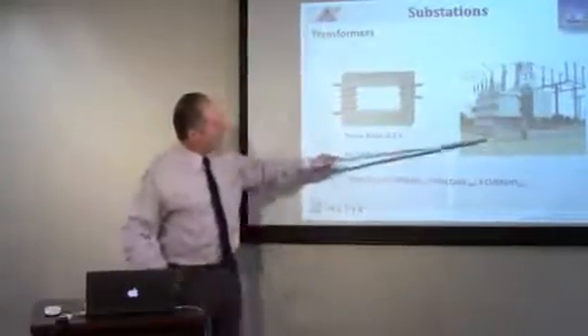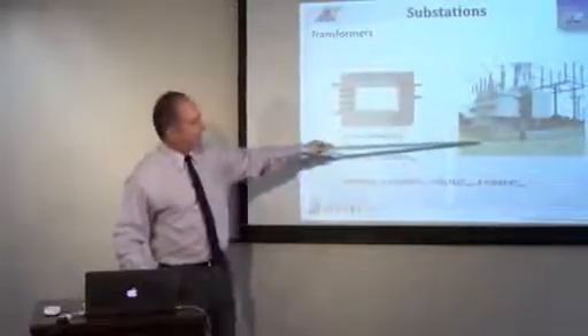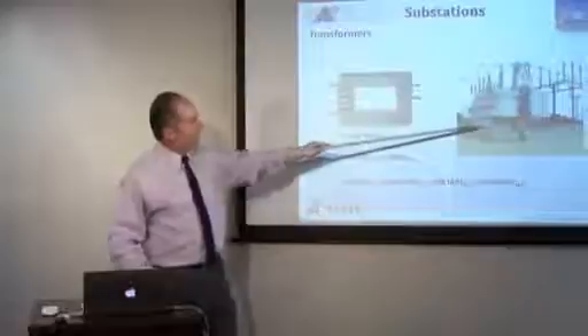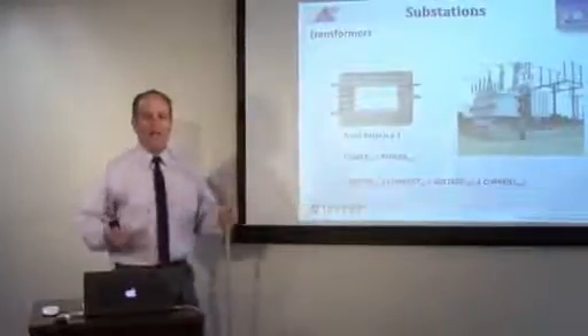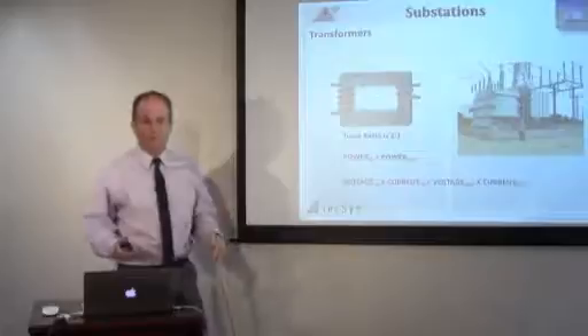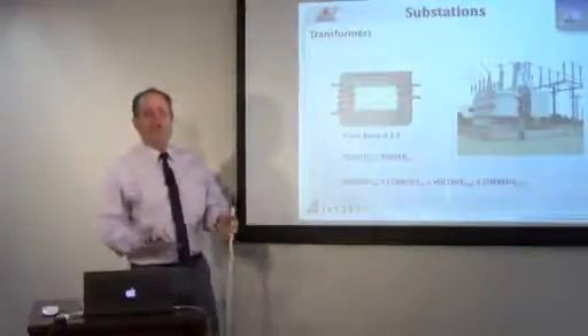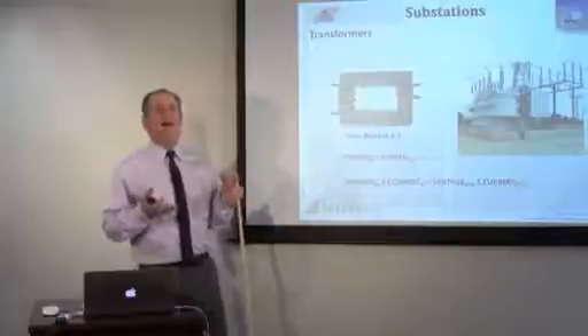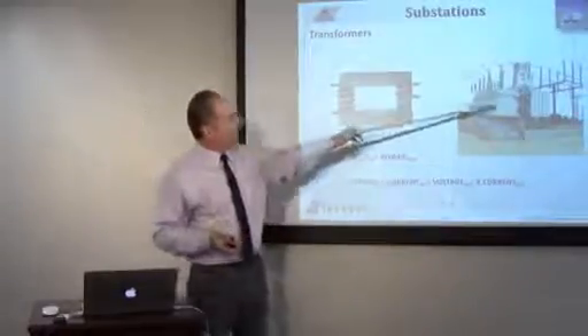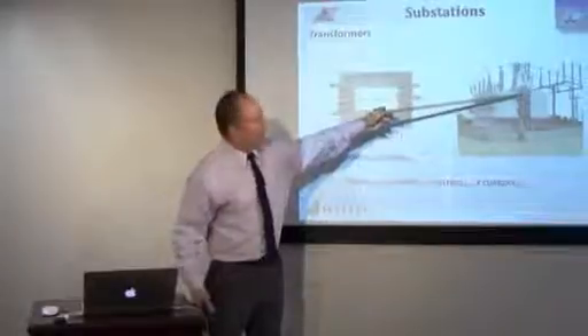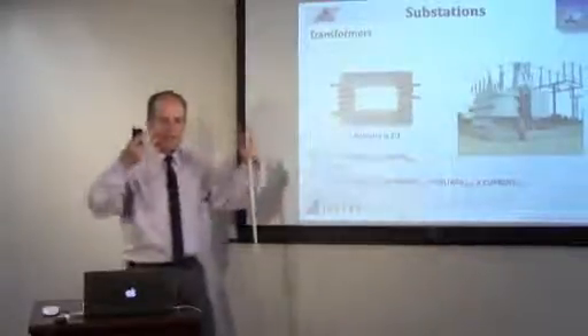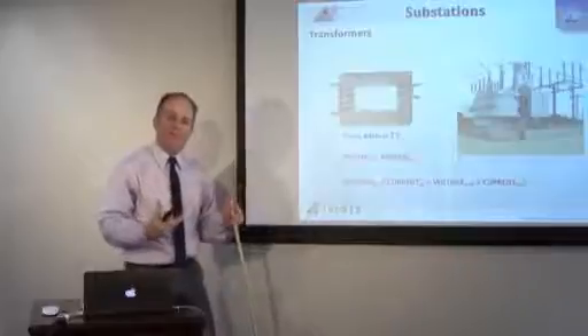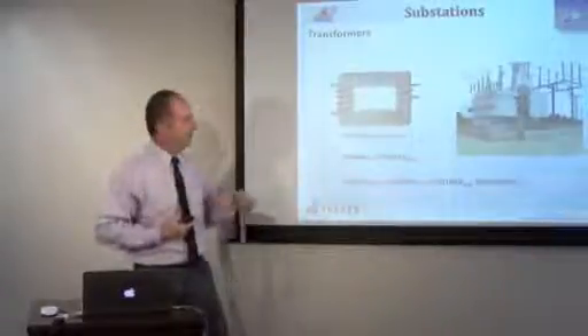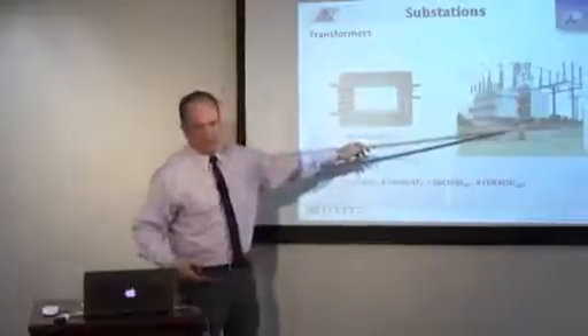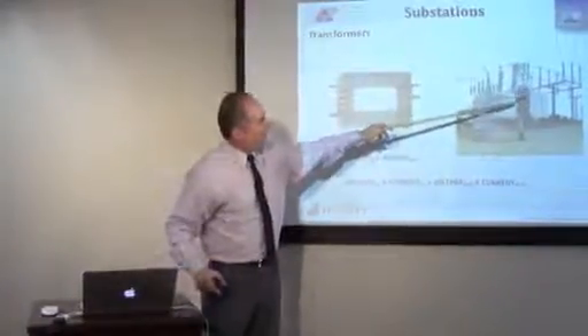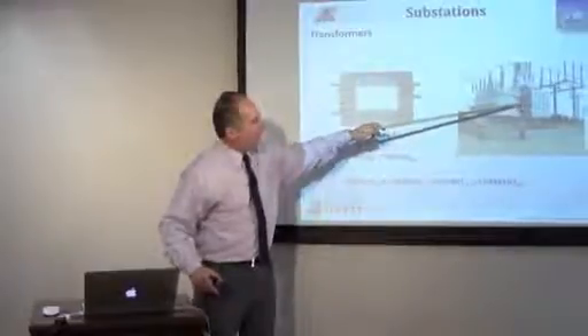This berm here is in case any of the oil inside the transformer were to leak; it would be contained. When the transformer gets hot from all the power flowing through it, from the resistive losses in the wires, the oil inside gets hot, and the hot oil rises to the top, goes through the pipes over here, and goes into these radiators where the oil is falling and being cooled by the air. That's convection cooling, and the oil goes back into the bottom of the transformer. And over here you have fans that help cool the oil as it's falling.